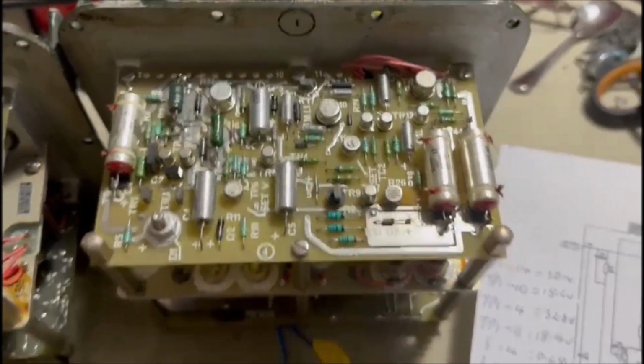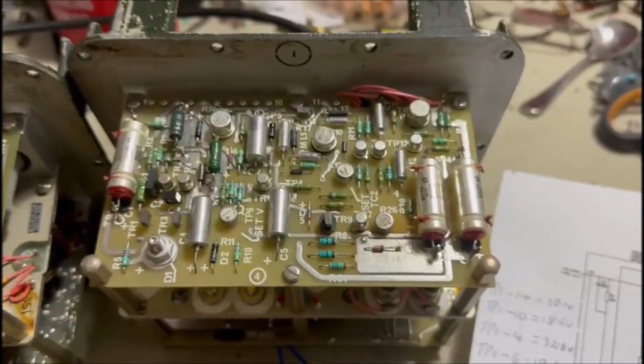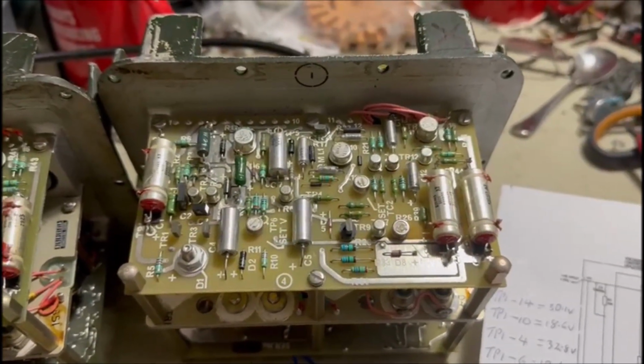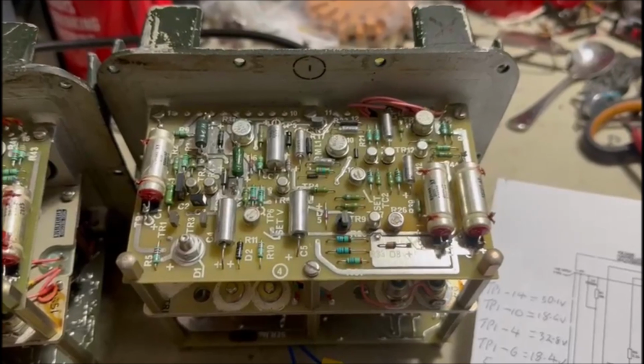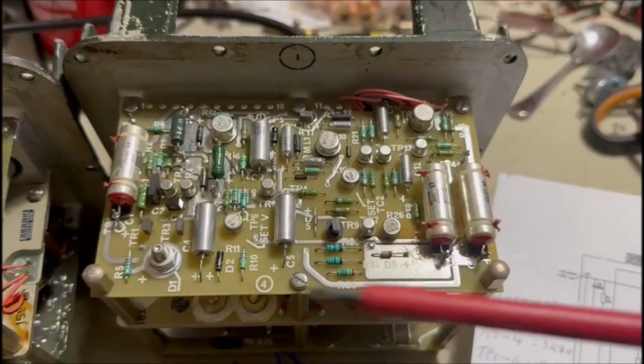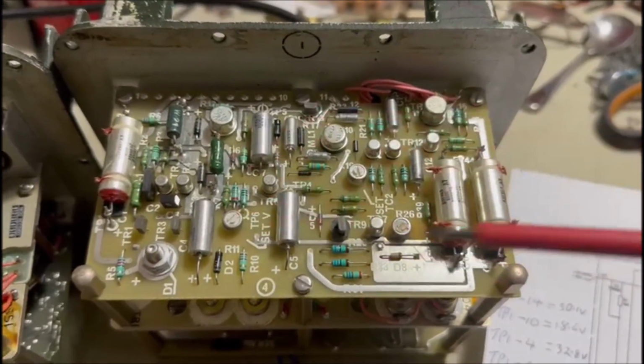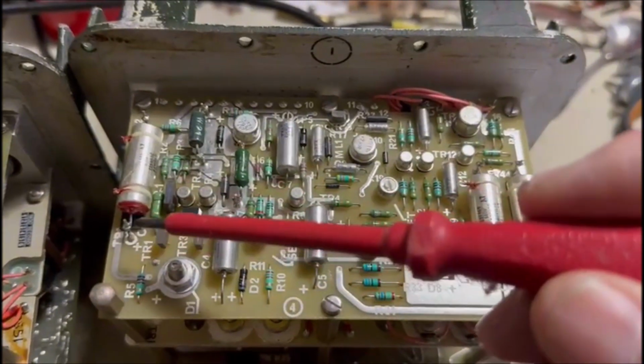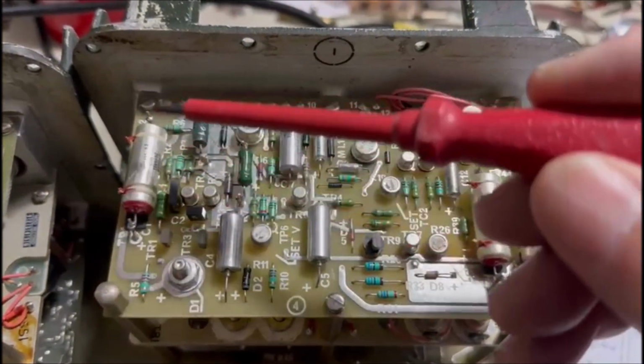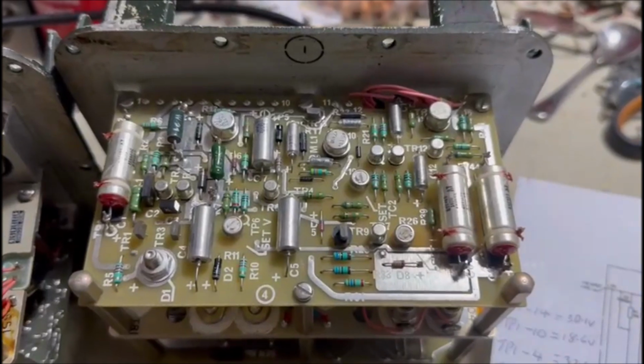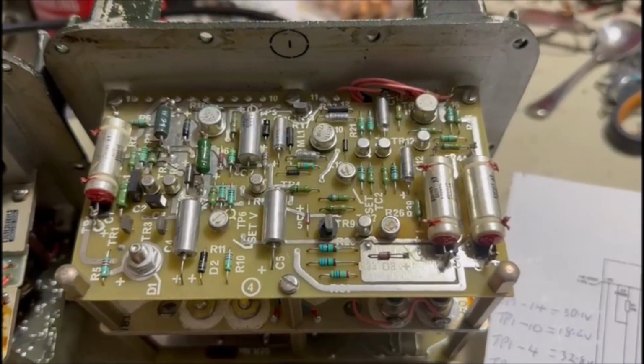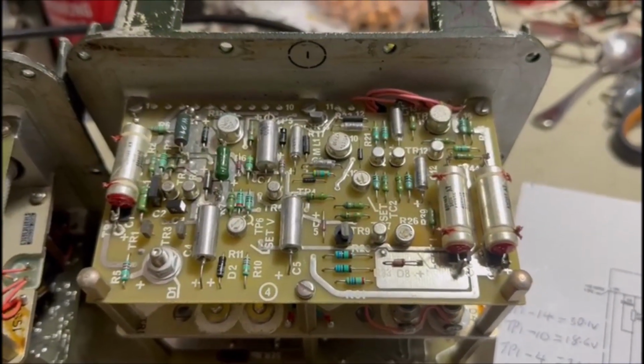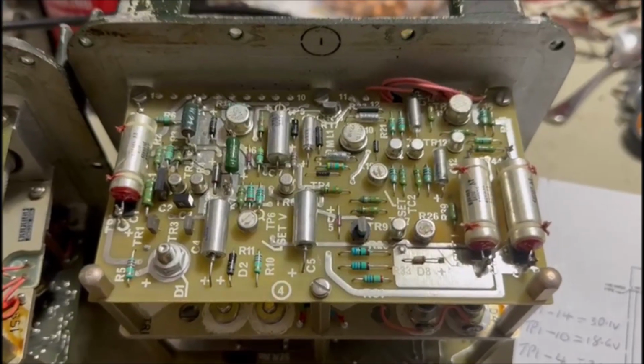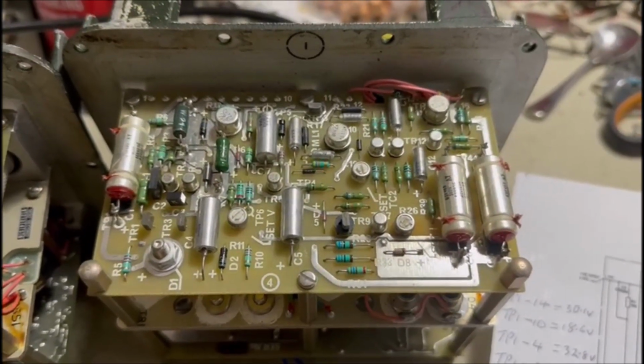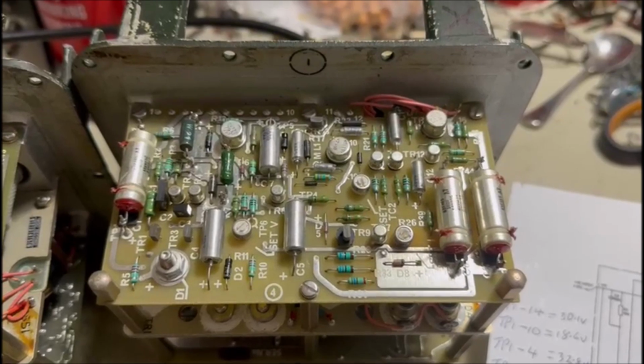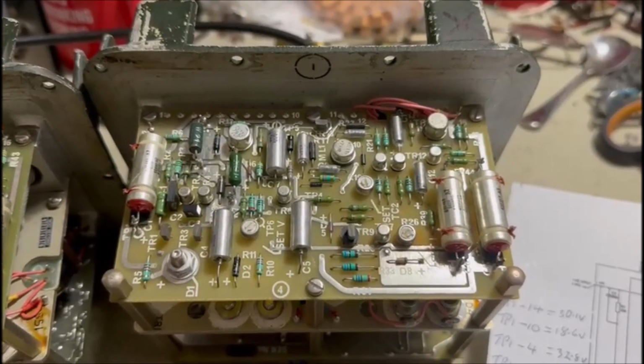The first thing that I do when I pull these battery chargers apart is to have a look and see whether I've got high voltage on the control board. There's a test point 1 and 2 across this capacitor here, and coming up from the transformer below, we should get a rectified DC voltage of about 60 to 70 volts that does all of the regulation and whatnot to charge the battery.